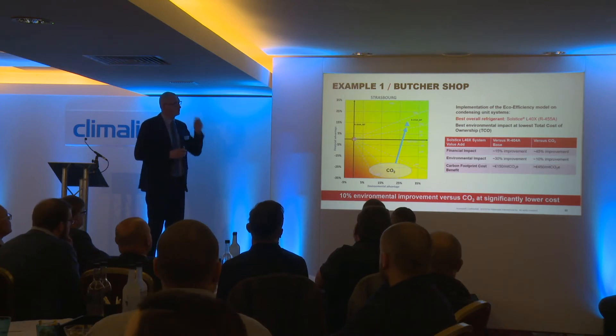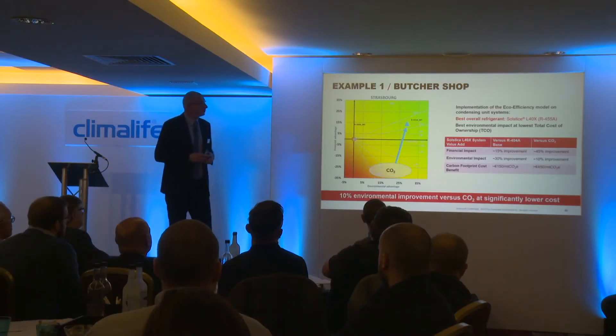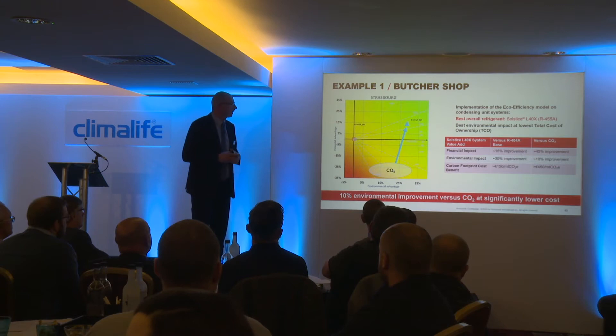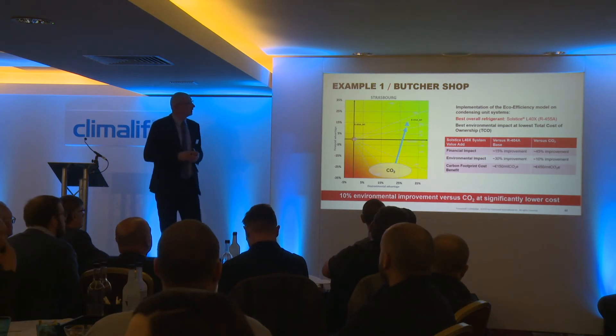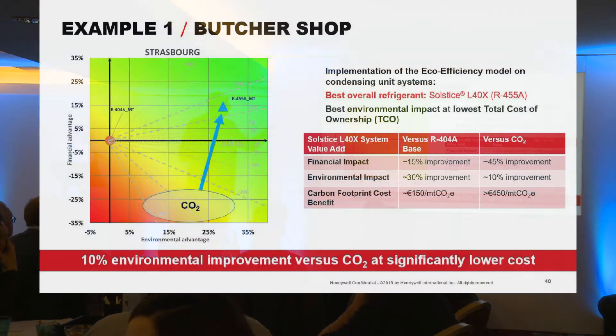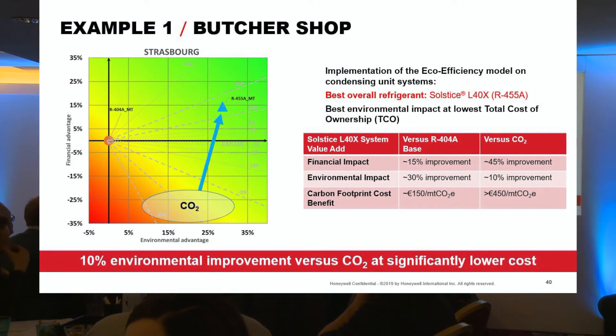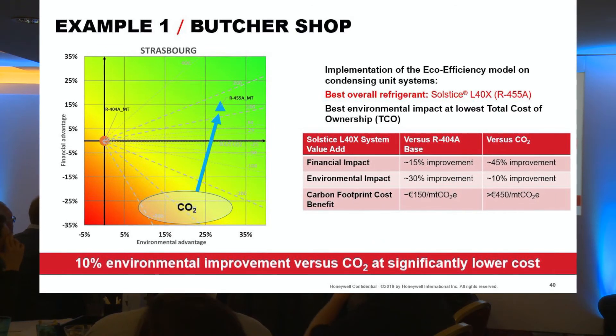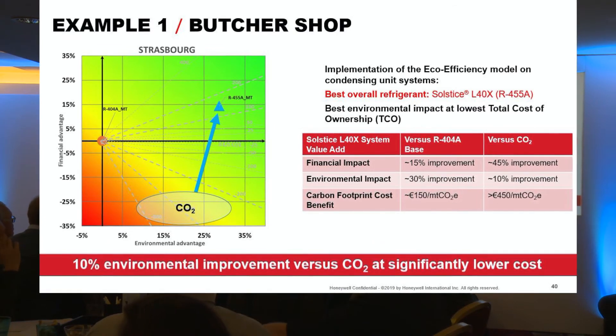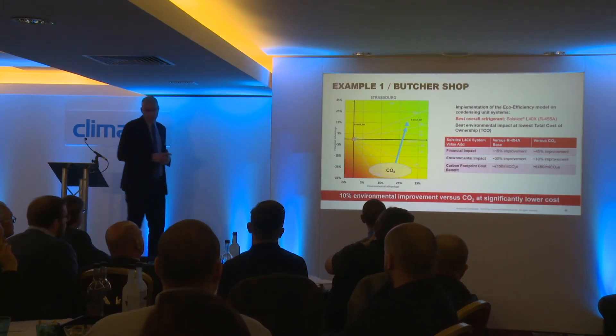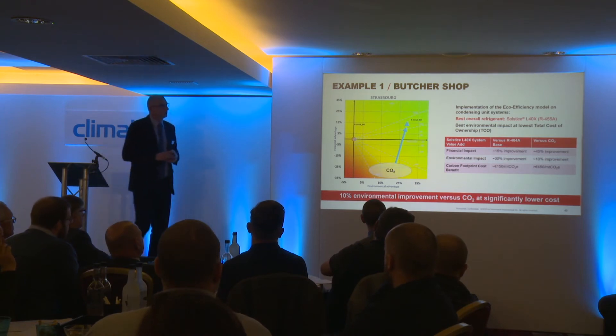I have examples of eco-efficiency simulation for the butcher shop. This is the eco-efficiency score for 455A versus CO2 condensing units. You can see that using 455A we can have approximately 45 percent improvement versus the CO2 system, and 10 percent improvement in terms of environmental impact.